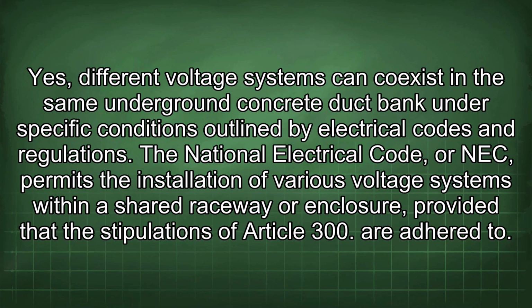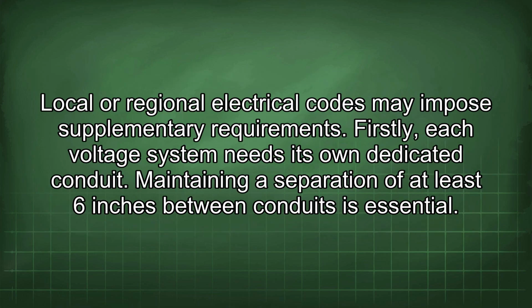Yes, different voltage systems can coexist in the same underground concrete duct bank under specific conditions outlined by electrical codes and regulations. The National Electrical Code, or NEC, permits the installation of various voltage systems within a shared raceway or enclosure, provided that the stipulations of Article 300 are adhered to. Local or regional electrical codes may impose supplementary requirements.